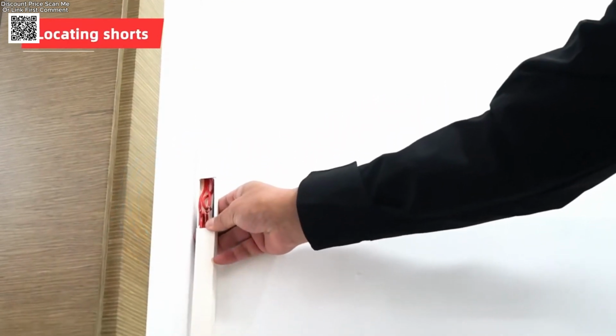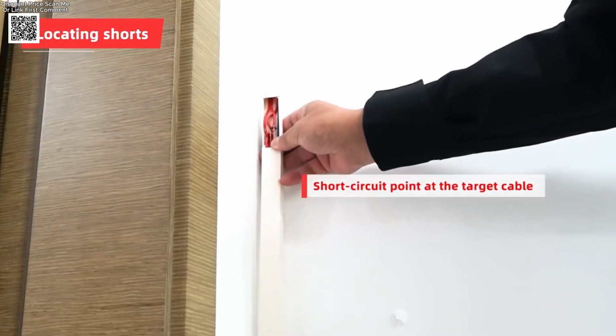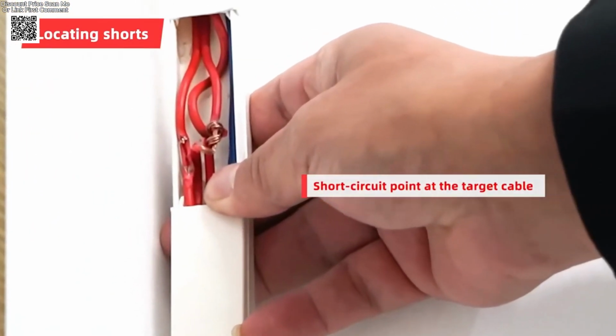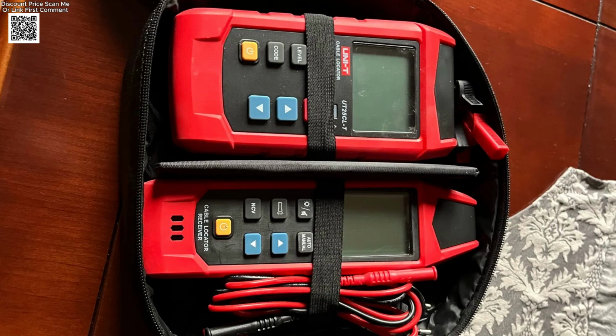The transmitter also measures voltage. It can read both alternating current and direct current, typically from about 8 volts up to 480 volts at 50 or 60 hertz. It indicates direct current polarity and includes an extra low voltage indicator. This is useful when you are unsure whether a pair of wires is actually carrying power or only a signal.